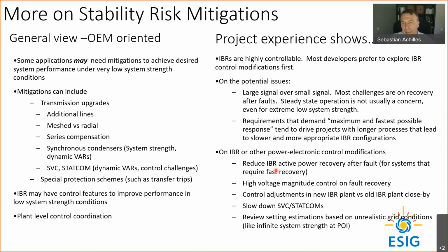In more concrete details, some of the modifications that are typically performed: slowing down the active power recovery is a very common aspect that is observed, necessary. This is not so much related to the inverter-based resource not being able to inject power quickly. It's kind of a combined aspect. So it's also related to the system not being able to take a lot of power very quickly when there is a big electrical distance between the point of interconnection and the rest of the network. High voltage magnitude control is important, as we saw in the previous plots.